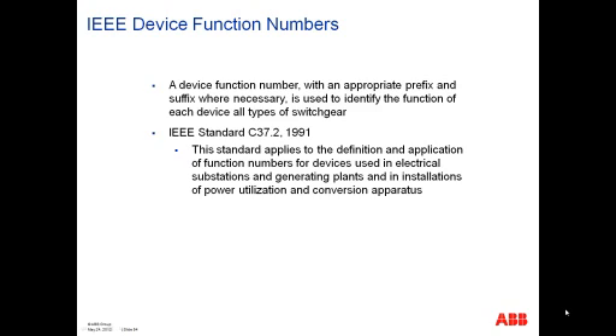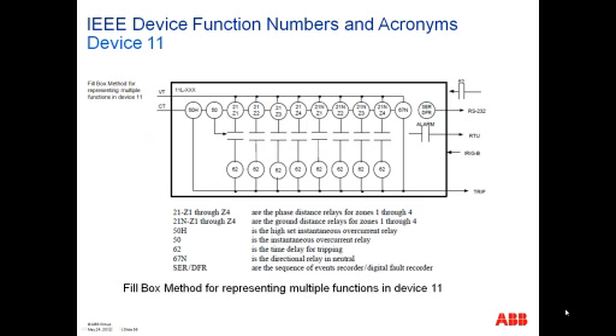So that's why you hear overcurrent relays, for example, an instantaneous unit might be referred to as a 50, which would be the device number, or a 50N, which would say that it is measuring the residual current. And then you would have a 51, which says it's an inverse time unit, and a 51N. The same can be said for 21, which is an impedance relay. But anyway, next slide.